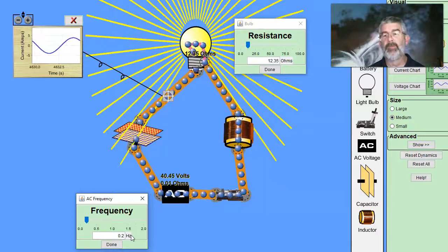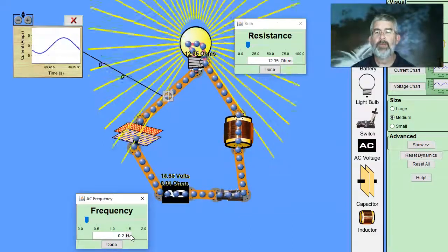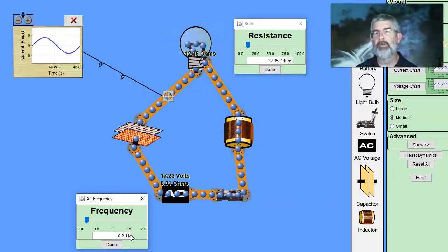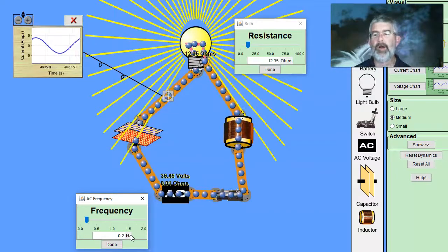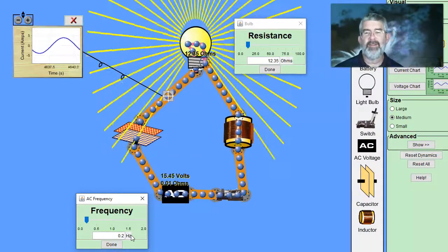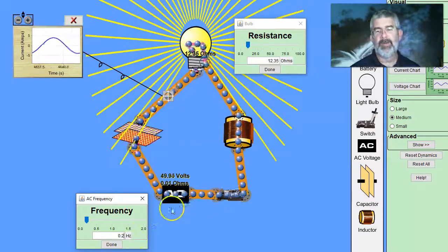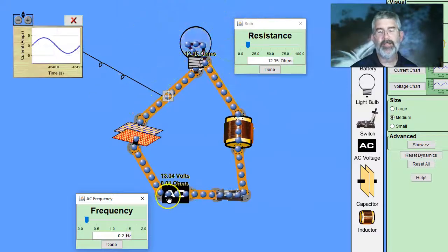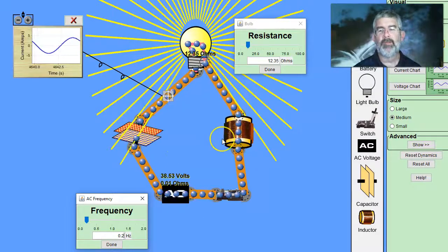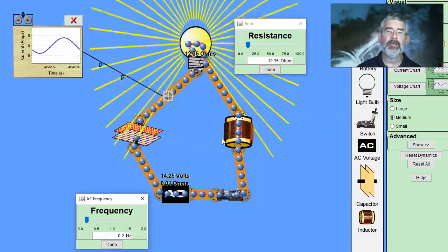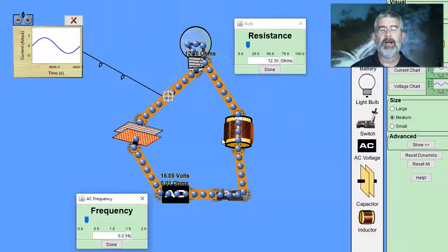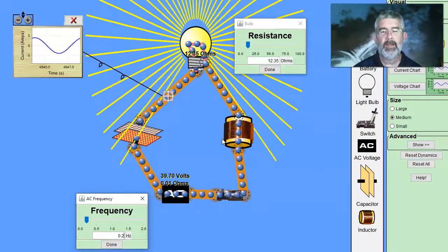And in the case of the parking lot lights, they're an arc tube, so they need a particular amount of amplitude to send the spark through the tube, and so they might not even light at all if you're not driving it right. So there's a play. When you're up there putting in a new capacitor, you're not changing the frequency of the forcing function. You're changing the natural frequency between the inductor and the capacitor, because you put a different capacitor in than what's supposed to be there, and so it may not work right.